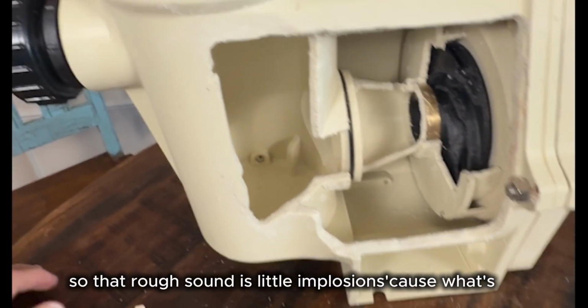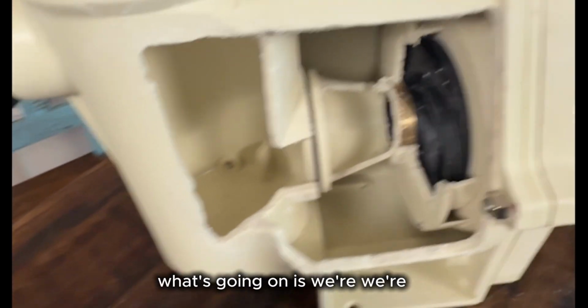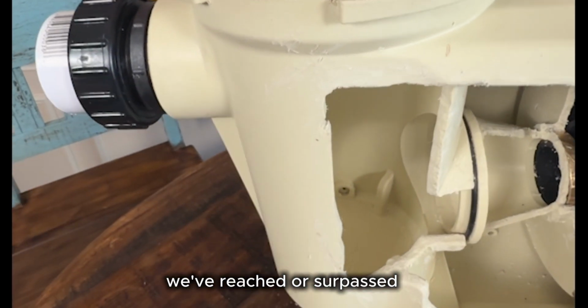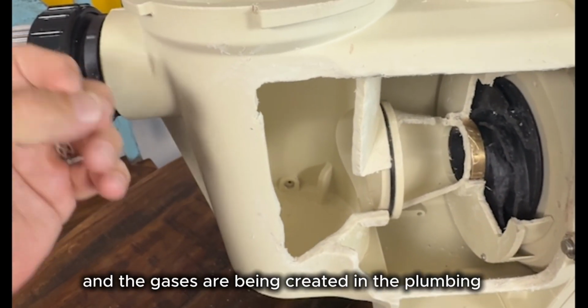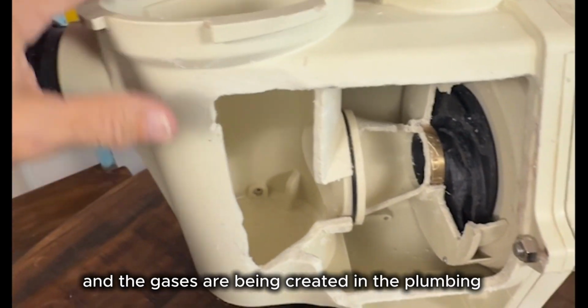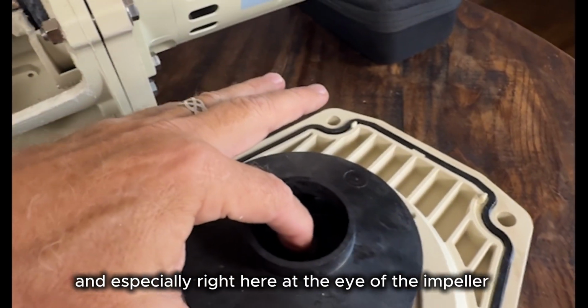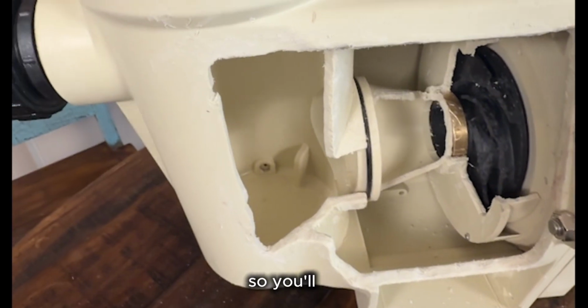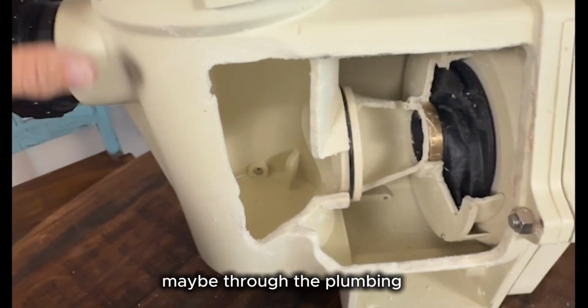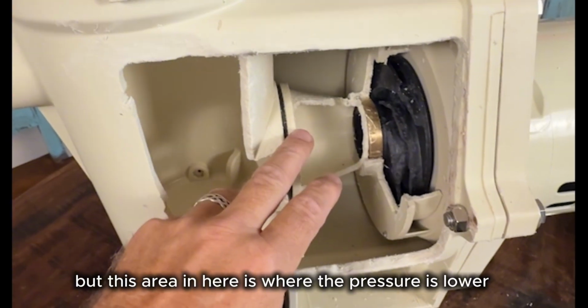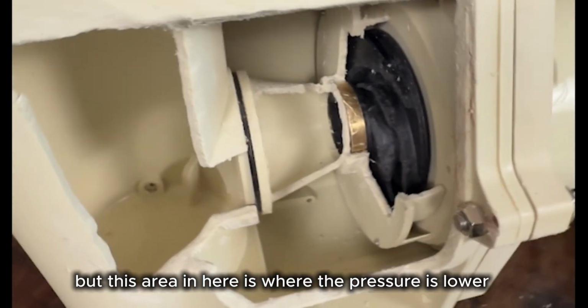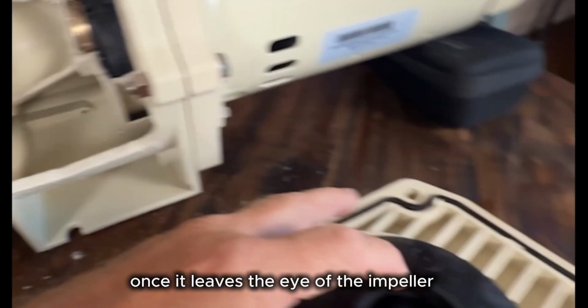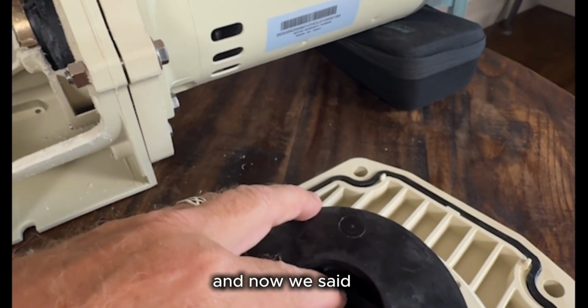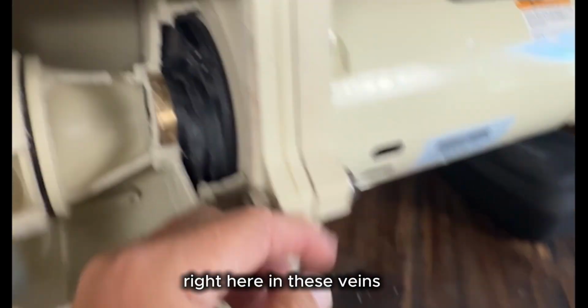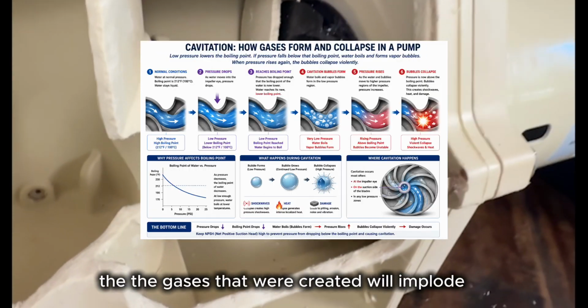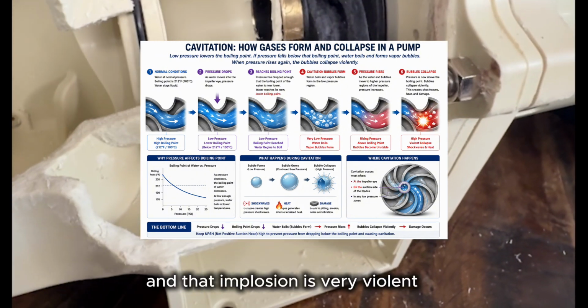So that rough sound is little implosions, because we've reached or surpassed the point where water is boiling and gases are being created in the plumbing, in the pump pot, and especially right here at the eye of the impeller, because that's our lowest pressure. You'll see some bubbles maybe coming from the valves, maybe through the plumbing, maybe some bubbles in the pump basket, but this area in here is where the pressure is lowest and the water will begin to boil. Once it leaves the eye of the impeller, we go from negative pressure to positive pressure right here in these vanes, and the gases that were created will implode, and that implosion is very violent.